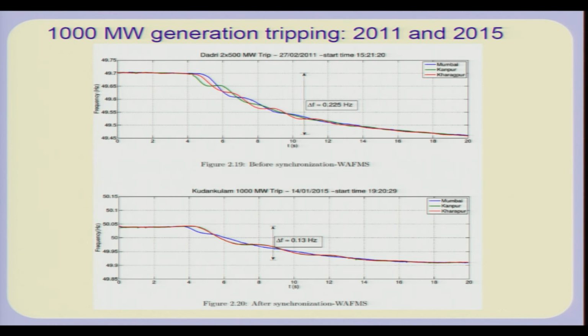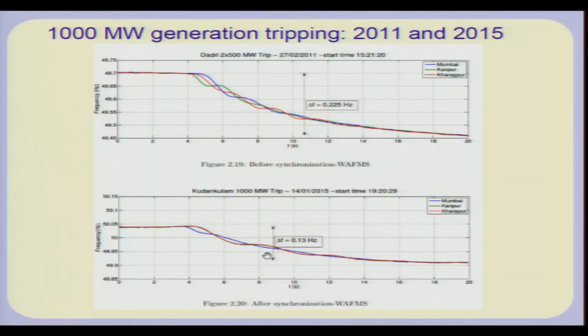So, if there is a sudden change in the load generation imbalance, you would expect the center of inertia frequency to fall, and the rate of change of center of inertia frequency is inversely proportional to the total inertia of the rotating masses in the system. You see that this inertia is much higher in 2015 because our grid has grown. A lot of generators have been connected to the grid, and therefore the rate of change has changed.